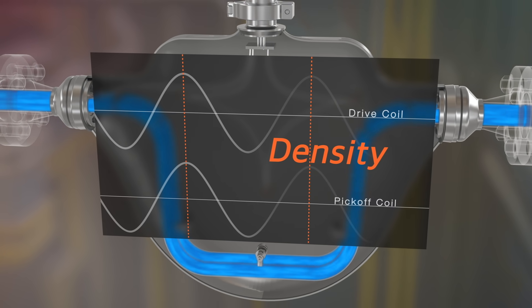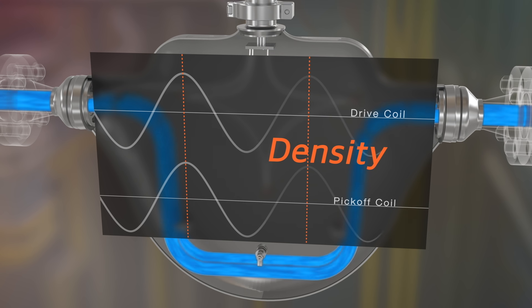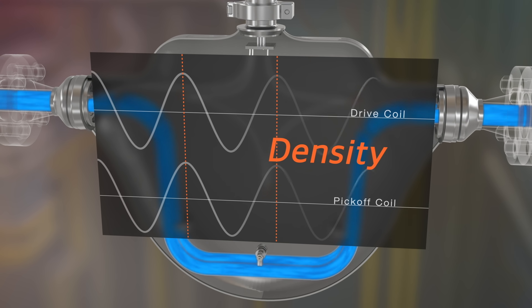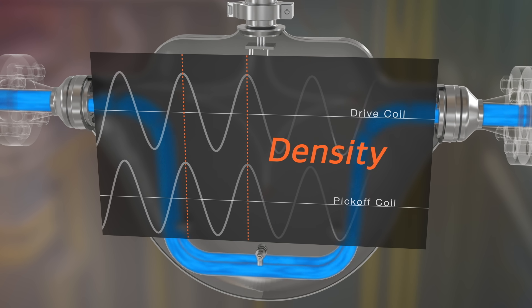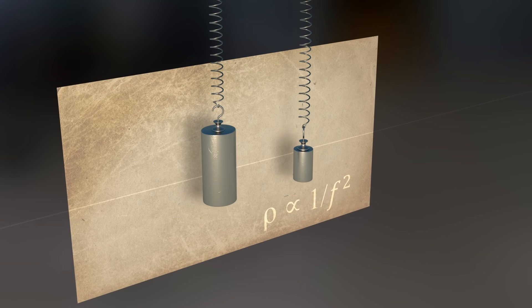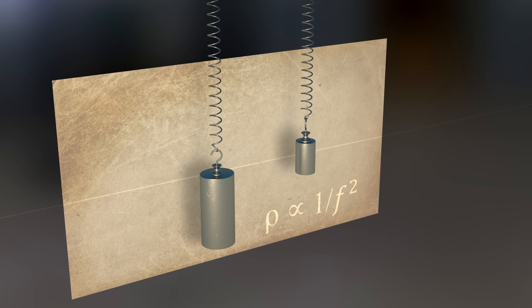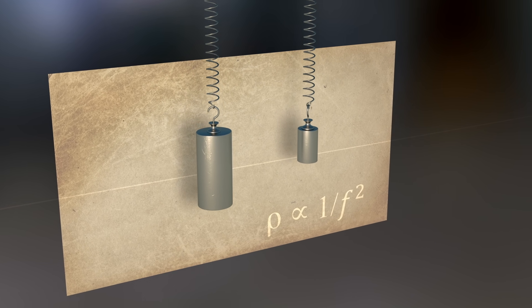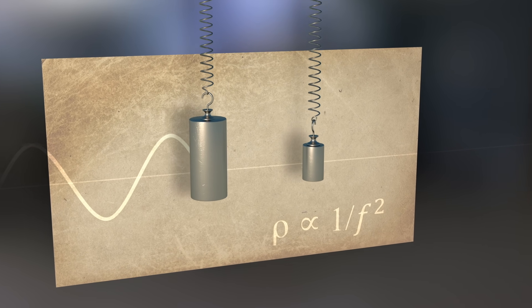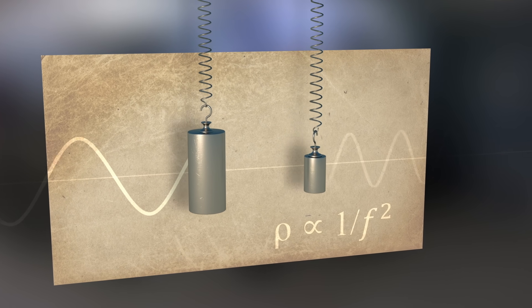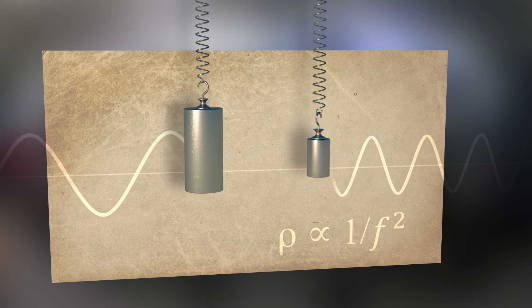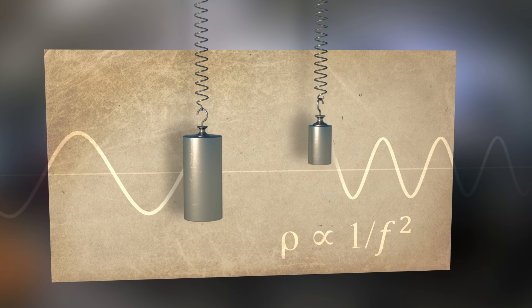When the liquid density changes, the vibrating frequency of the tubes also changes. Similar to a spring and mass system oscillating at its natural frequency, a larger mass oscillates at a lower frequency while a smaller mass oscillates at a higher frequency.